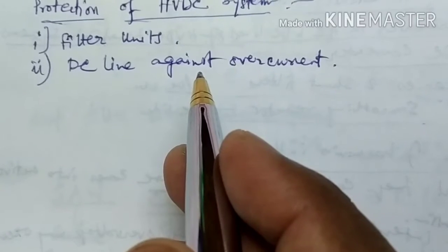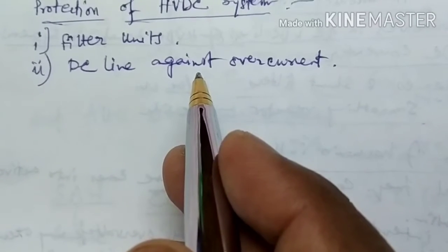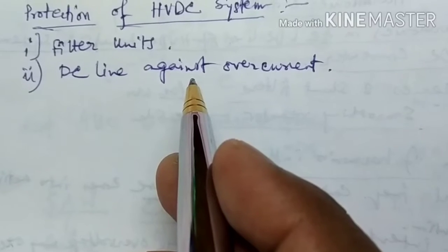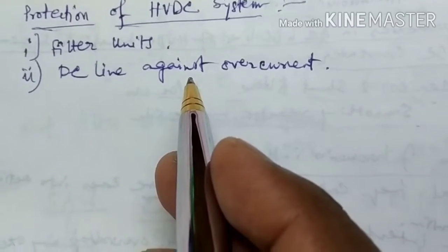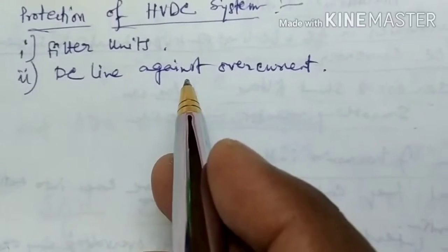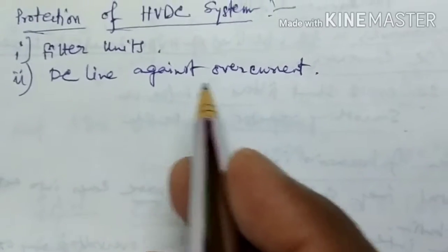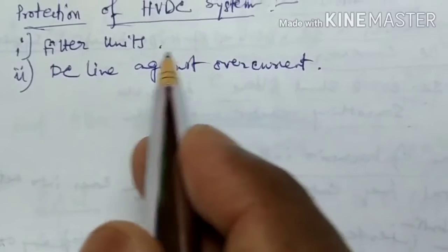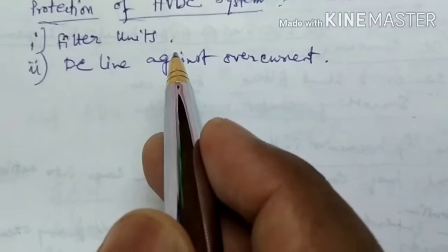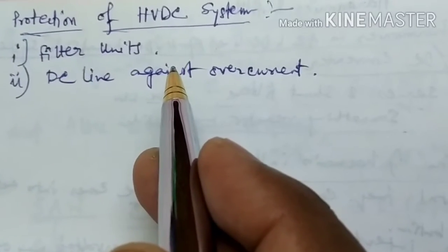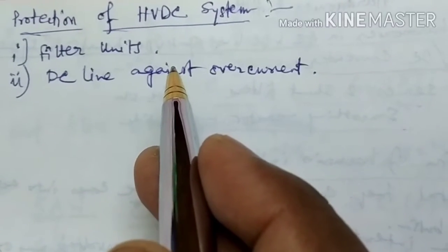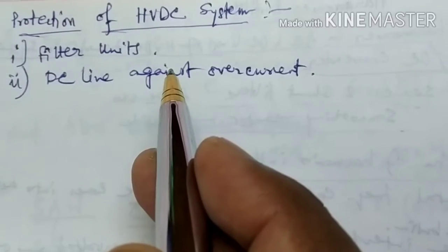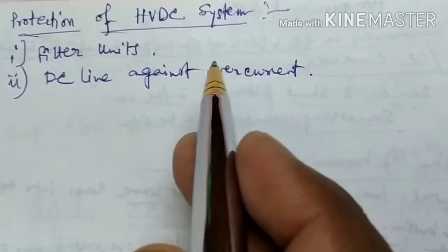A few of them are connected in parallel to make up the required kVAR. Each rack is protected by a HRC fuse unit, and further the filter arms are equipped with overcurrent relays which respond to both power frequency and also harmonic voltage.